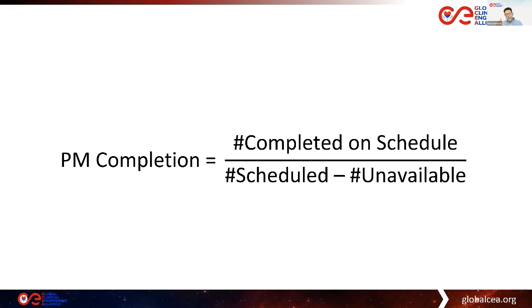That gives you an overview of how well you're adhering to the schedule you've put together. Now, the one other factor on this screen is minus the number of devices that are unavailable. For example, if a device simply cannot be located after working hard to find it, you can't do the PM on it. If the device is in use with a patient, we cannot interfere with patient care to do the PM. So in your metrics, you can take into account that sometimes PM is unavailable. All of that is discussed in one of the references I'll show you later, about how to work with the various versions of this performance metric to make sure the work gets done on an appropriate schedule.